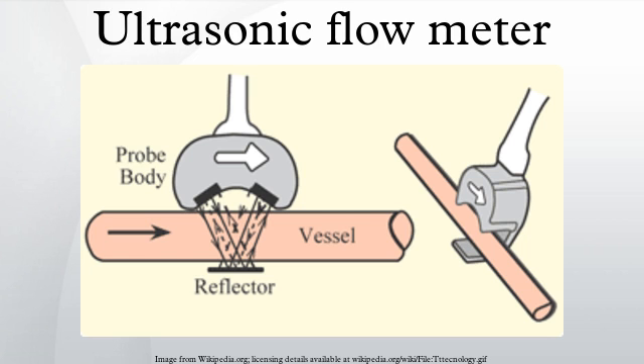Doppler shift flow meters: Another method in ultrasonic flow metering is the use of the Doppler shift that results from the reflection of an ultrasonic beam off sonically reflective materials, such as solid particles or entrained air bubbles in a flowing fluid, or the turbulence of the fluid itself if the liquid is clean. Doppler flow meters are used for slurries, liquids with bubbles, and gases with sound-reflecting particles.